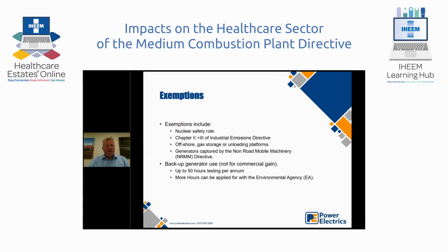Probably the best news for anybody working in a hospital or the NHS is that if you're using the generator purely for backup purposes, up to 50 hours a year for testing, and unlimited in an emergency if you lose your supply, then you're exempt from this legislation. The best way to put it: if you're not using the generator for commercial gain and it's performing a life safety function, you don't need to worry about this standard. You may have to log the hours and the fuel, which we'll come to later regarding permitting.